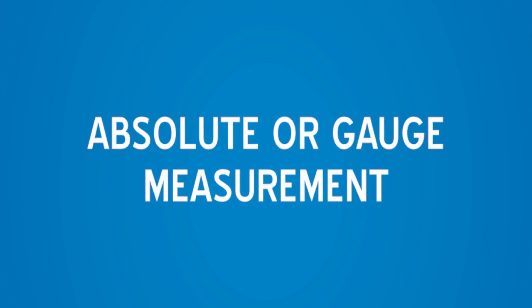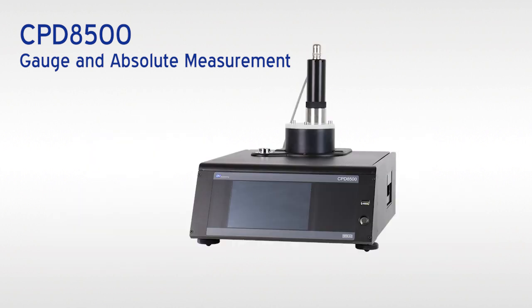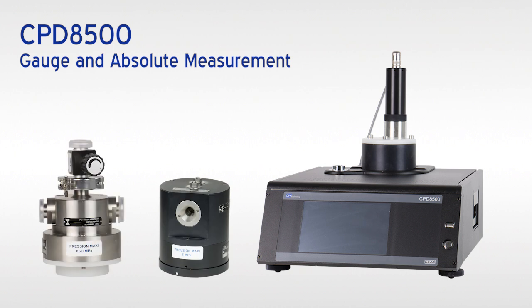The CPD 8500 can operate in absolute or gauge mode by switching the reference pressure and measuring heads. One base can adapt to a variety of measuring head ranges to allow different pressure modes in one instrument.